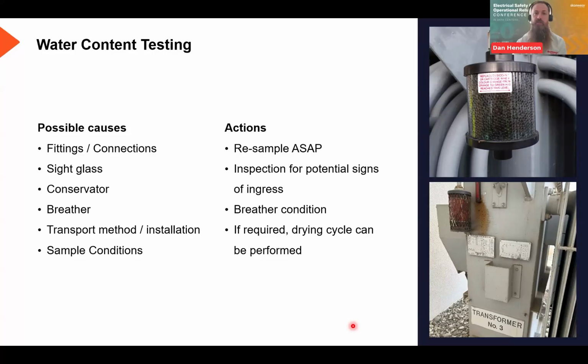So free breathing transformers are designed so that as the temperature increases and decreases, the oil level expands and contracts, and those desiccant breathers will allow that pressure to be pushed out or in as the oil contracts or expands. And obviously any moisture in that environment, whether it's humid, wet outside, or cold and damp in that space, that silica gel breather, that desiccant breather, is there to absorb that moisture, so nothing should get into the transformer. Likewise, where you're getting any evaporation inside the transformer, it should be able to escape through and get captured within that breather and not held in the oil. So that's what that's there for.